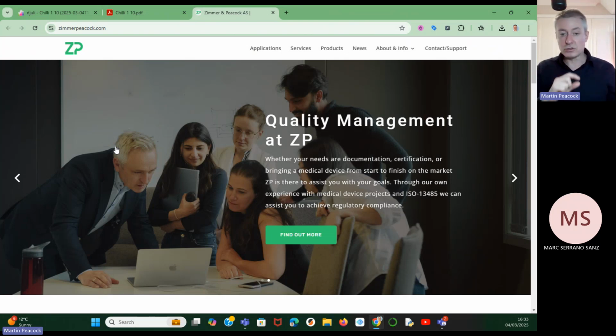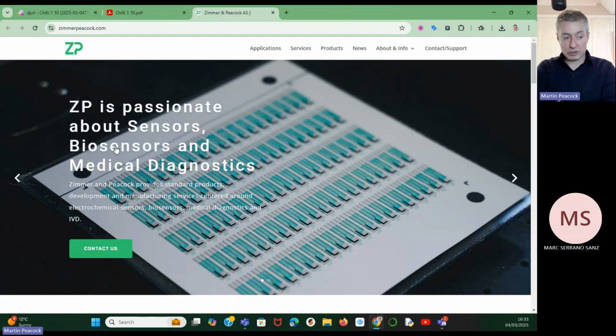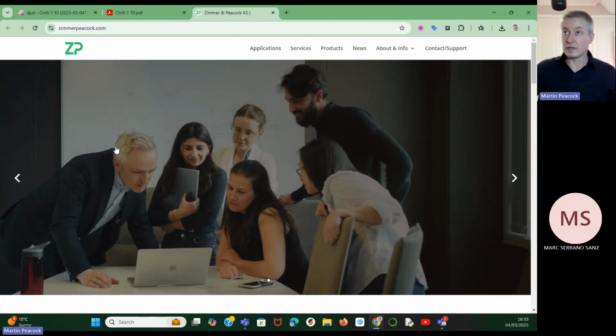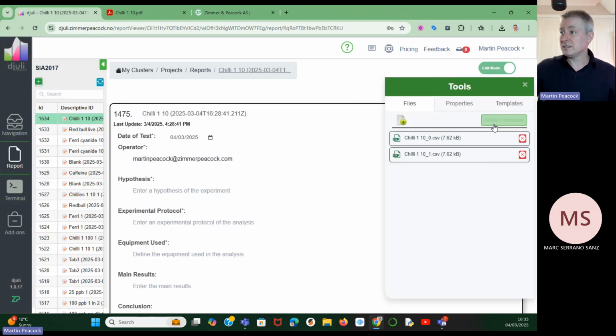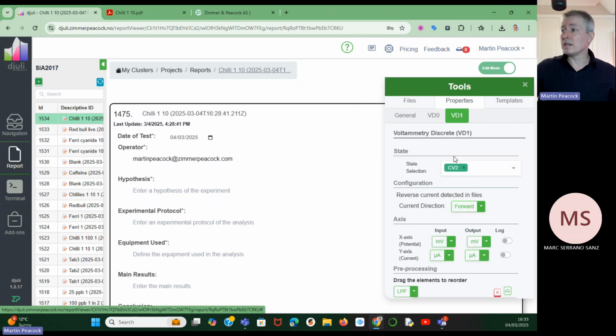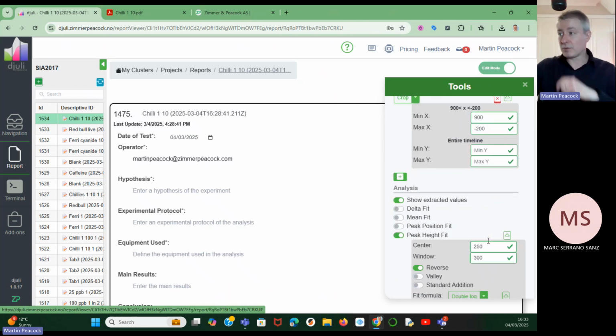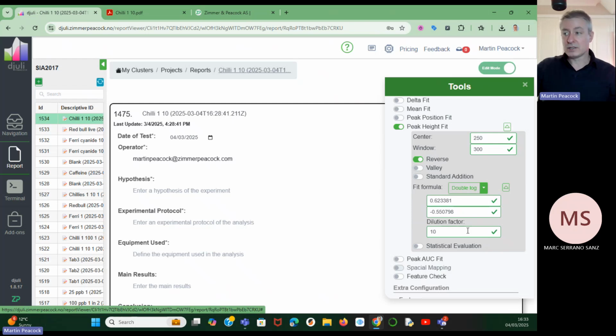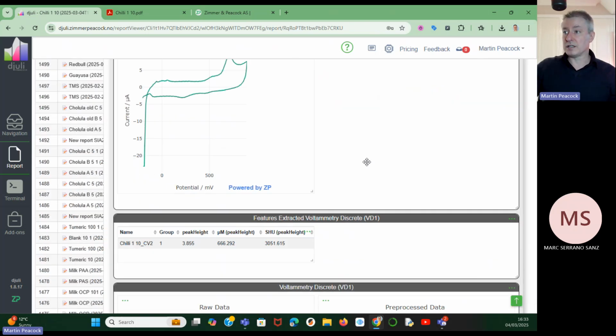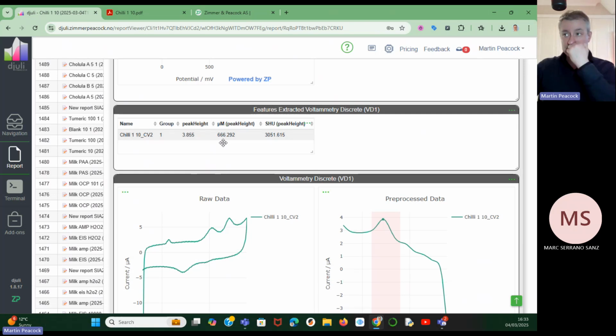No, as long as you do some calibration experiments where you try the assay or the sensor with different calibrations, and therefore we can figure out what your gradient for the calibration is and what your offset is, as long as that's all figured out, then we can turn the raw signal into, in the first instance, a peak height, for example, and then using the calibration, turn it into a number and send it back to the phone. So suddenly the system is actually leaving the lab.